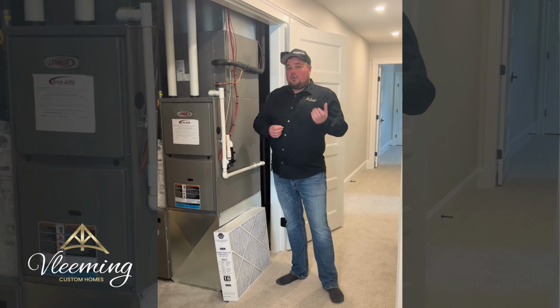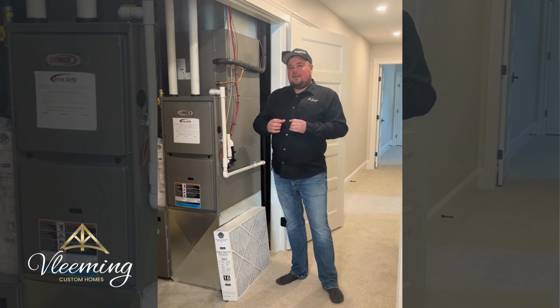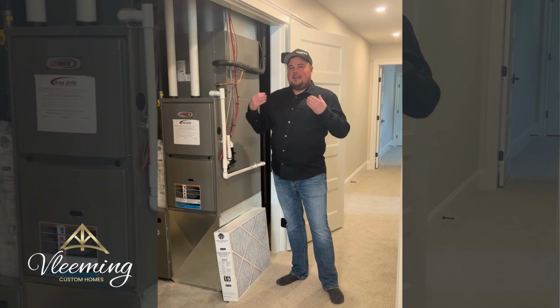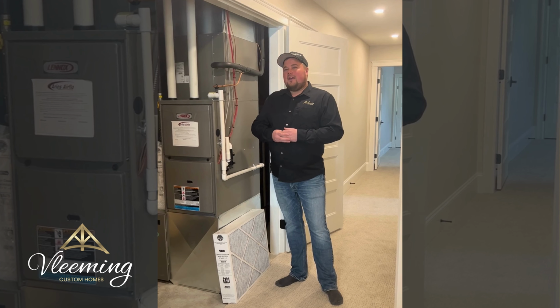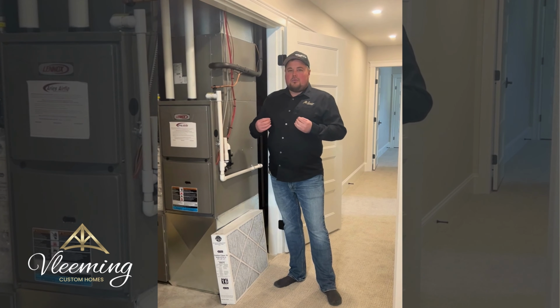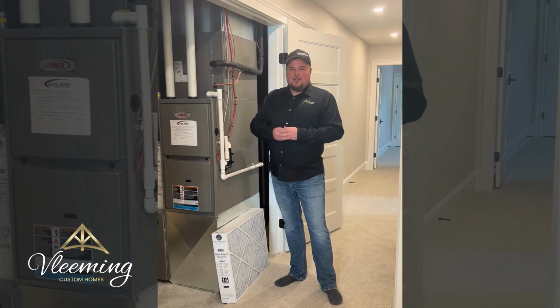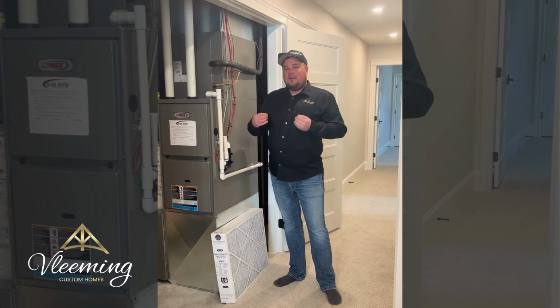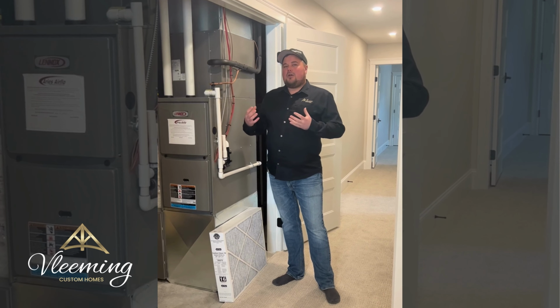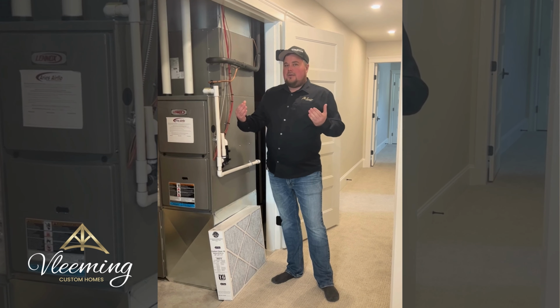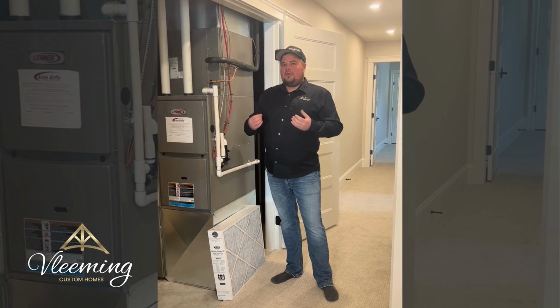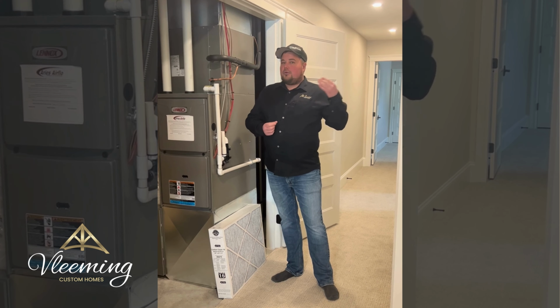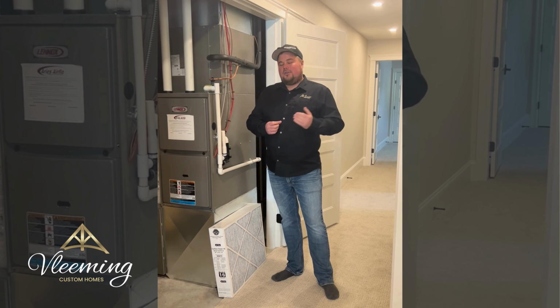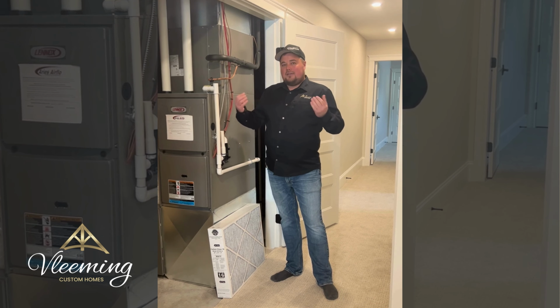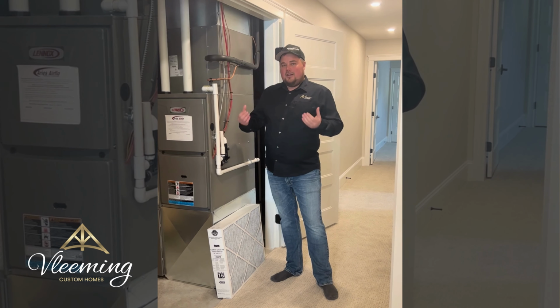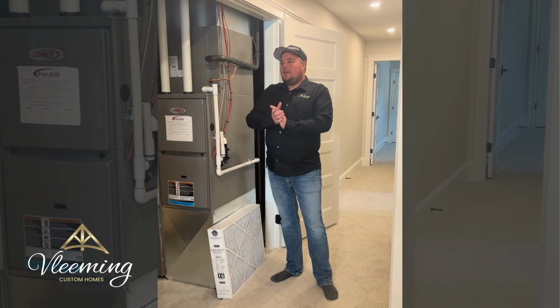It's not as simple as just running a bunch of pipe. The size of the pipe and the size of the ductwork affects the heating and cooling abilities of your home. So it needs to be sized for every room. So what we do is we do a heat loss calculation on every room to determine, for a master bedroom, how much heating requirement is it actually going to have? Maybe that master bedroom has 3 exterior walls, a lot of windows. It's going to lose more heat than the room that has less exterior walls and less windows. You need to make sure that the ductwork and the supply air to that room are adequate and are supplying what's required. That's a part of it.